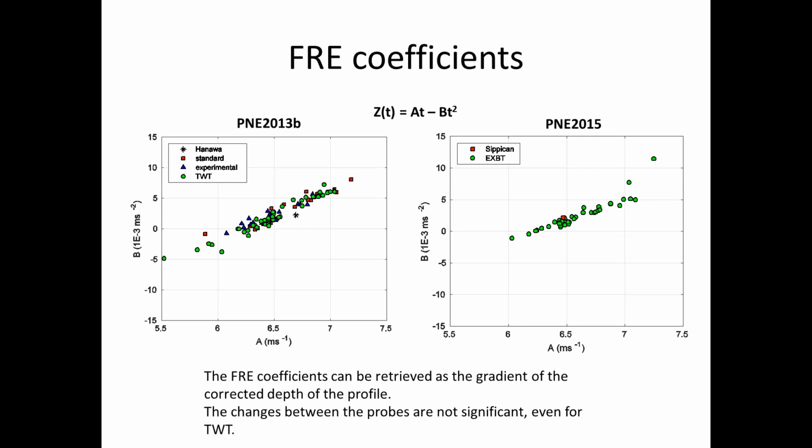Some people estimate that in a two-step process, so they just get the offset, for example, when you have a thermostat in the water and you don't have too much temperature variability. Sorry, I'm talking about the temperature offset.